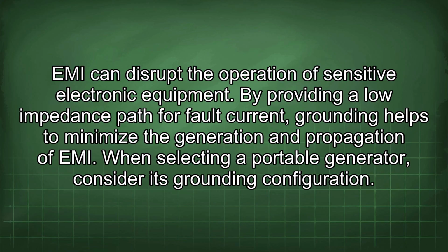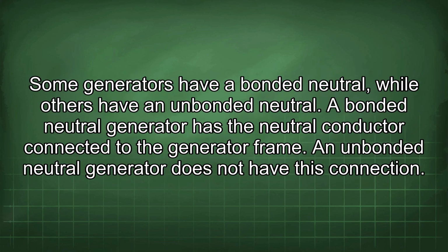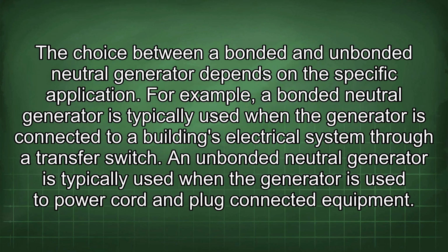When selecting a portable generator, consider its grounding configuration. Some generators have a bonded neutral, while others have an unbonded neutral. A bonded neutral generator has the neutral conductor connected to the generator frame. An unbonded neutral generator does not have this connection. The choice between a bonded and unbonded neutral generator depends on the specific application.